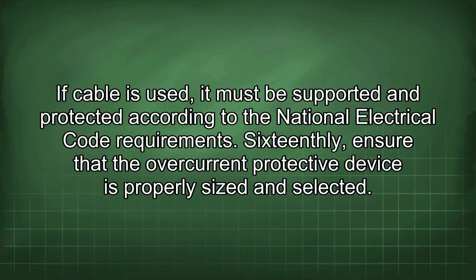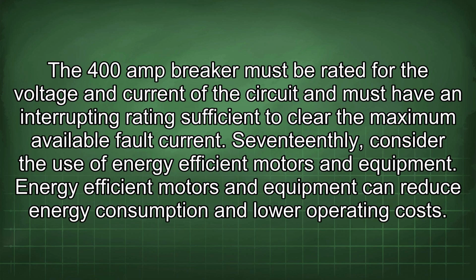16thly, ensure that the overcurrent protective device is properly sized and selected. The 400 amp breaker must be rated for the voltage and current of the circuit and must have an interrupting rating sufficient to clear the maximum available fault current.